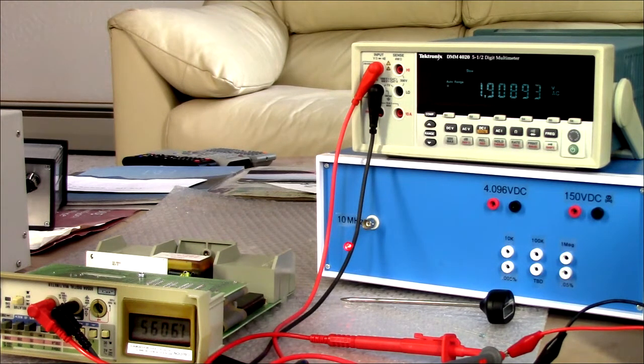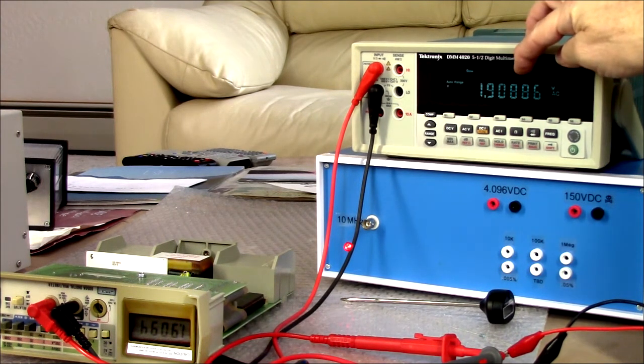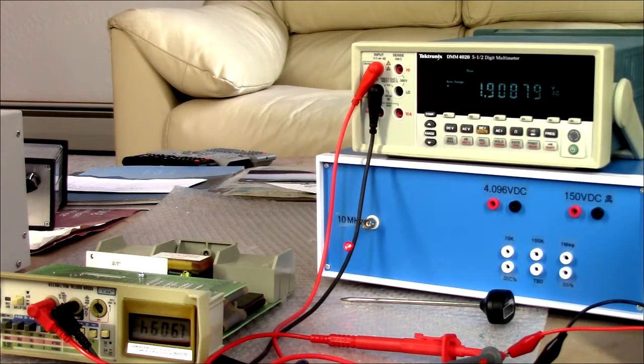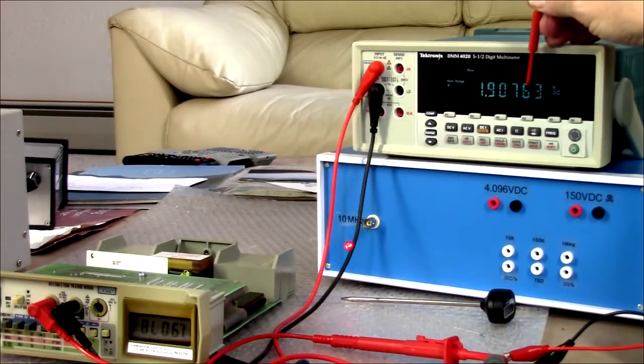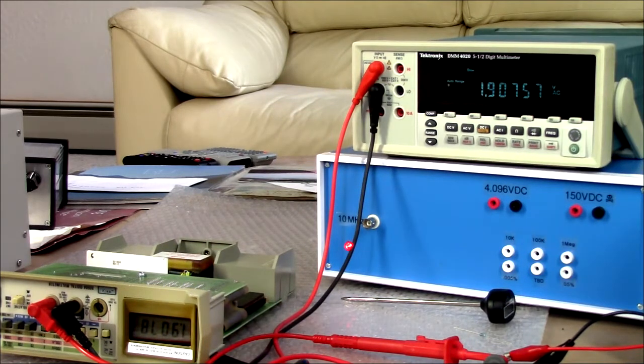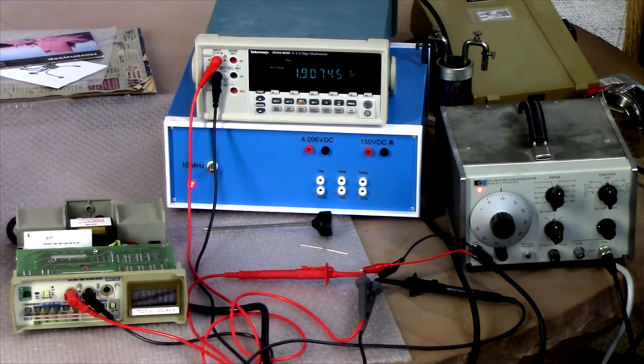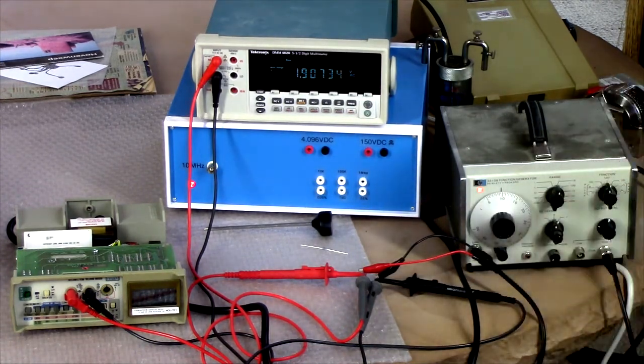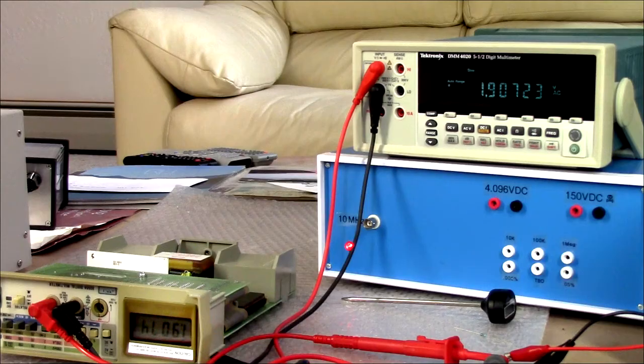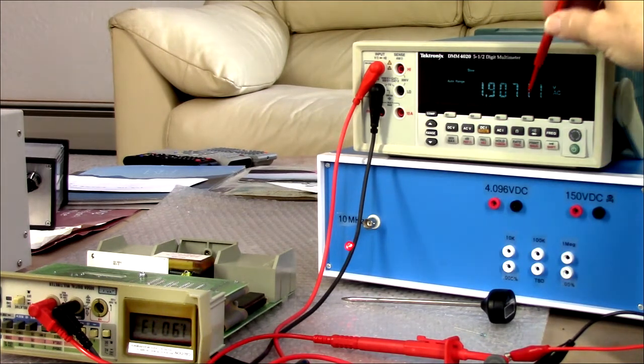1.909. 1.9095. 1.90, let's see, 88. That says 94. It's off by about 5 counts. This is R7. All right. 7.6, 7.8. I don't think I'm going to get any closer than that. It turns out R7 and R29, which is the next one, are interacting adjustments. Repeat until both are within their limits. Oh, and that's plus or minus 5 counts to consider it in spec here. And so we're definitely within that.